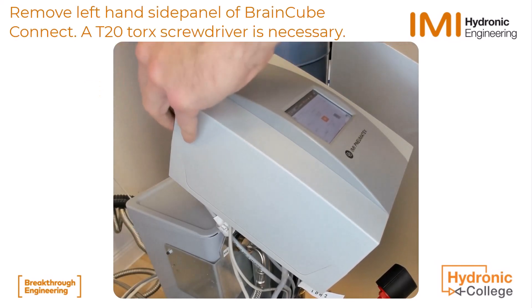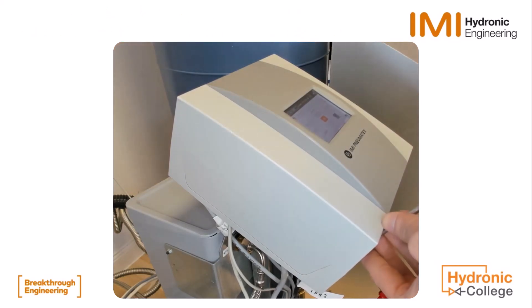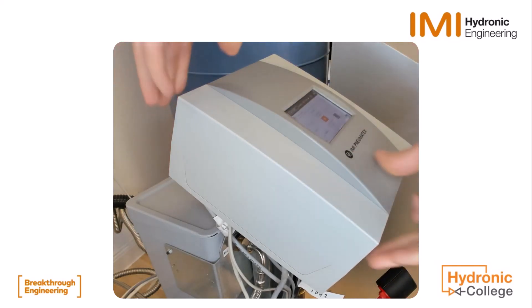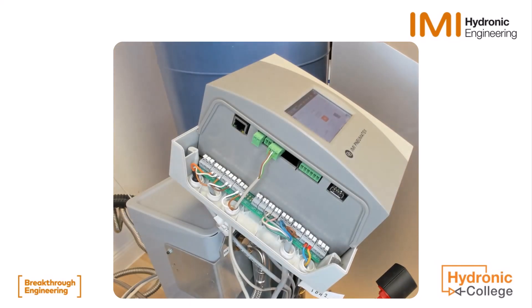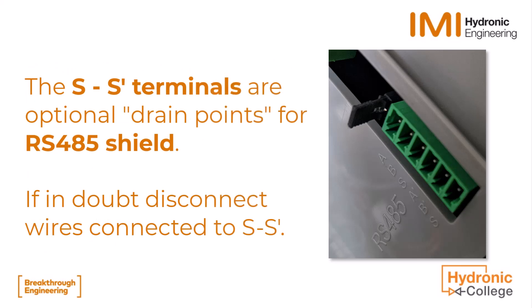There are separate videos showing both RTU and TCP wiring and commissioning on the BrainCube Connect. The Ethernet and RS-485 connections used for respectively Modbus TCP and Modbus RTU are on the left-hand side of the BrainCube Connect. For the RS-485 wiring, check the order of A and B wires in the complete RS-485 network and the position of the termination resistance. The S-Terminal is for the cable shield — for test purposes, it can be disconnected to see if it makes a difference.